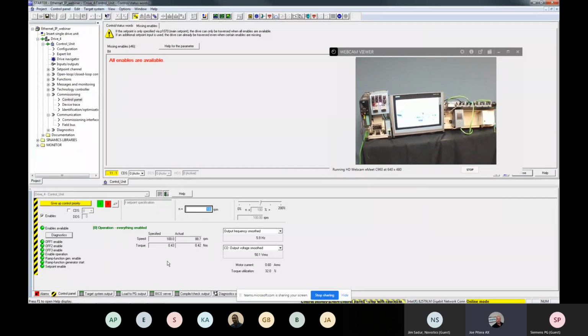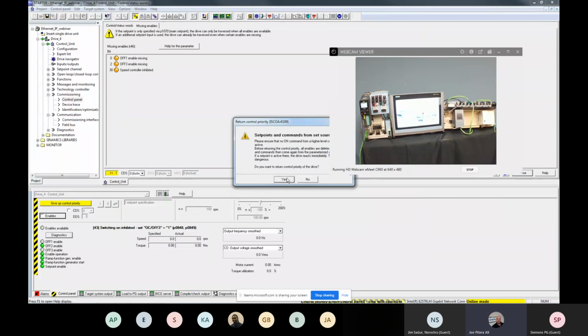All right, so that was pretty easy to commission the drive and get it running. We can see that there are some green lights on it as well for Profinet communications. And what I'm going to do now is stop the drive. And we actually finished commissioning this drive, so congratulations on that. I can show that by giving up the control priority here.